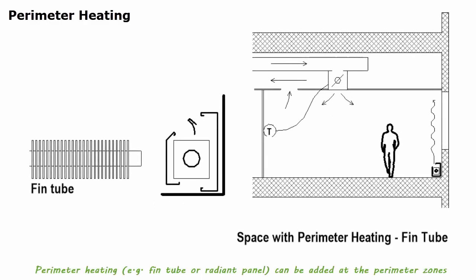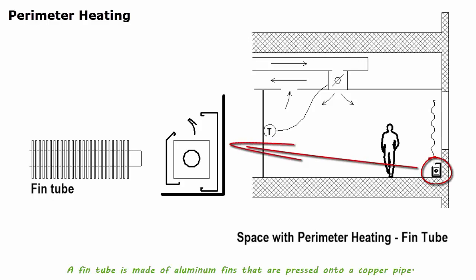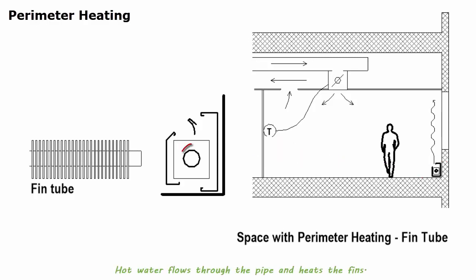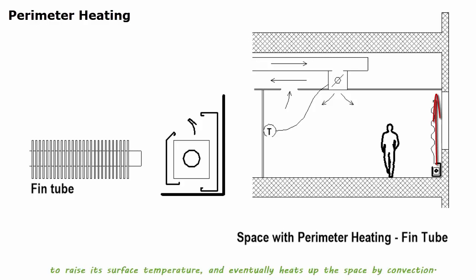Perimeter heating, such as fin tube or radiant panel, can be added at the perimeter zones of the building, usually below the windows, as a supplementary heat source to elevate the radiant temperature. A fin tube is made of aluminum fins that are pressed onto a copper pipe. Hot water flows through the pipe and heats the fins. The space in between the fins allows the air in that space to be heated. As warm air rises, it exits the housing, heats the window above to raise its surface temperature, and eventually heats up the space by convection.